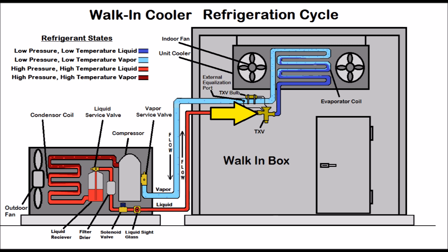The refrigerant then goes through the thermostatic expansion valve, which is a metering device. It lowers in pressure and lowers in temperature, turning into a low pressure low temperature liquid refrigerant — actually about 80% liquid and 20% flash gas, but shown here as a low pressure low temperature liquid.